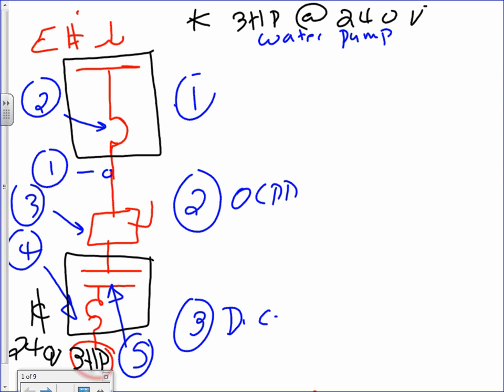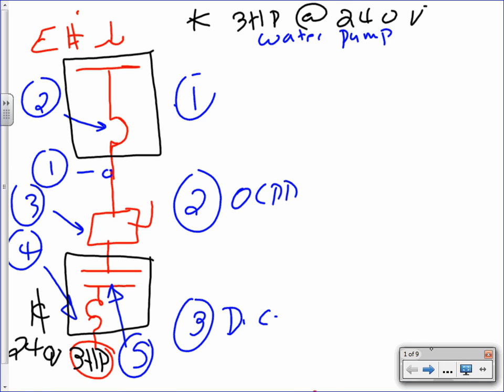I started with my panel. Here's my panel, and here's my pump at the bottom. From my panel all the way to my pump, I need to size the branch circuits. This is my branch circuit. The second one is the overcurrent protection device. The third one is the disconnect. The fourth one is called the overload. The fifth one is the controller. Any comments, guys? Any questions about what we will be required to do for the system? Everybody draw that one. I'll give you a few seconds here to draw that.